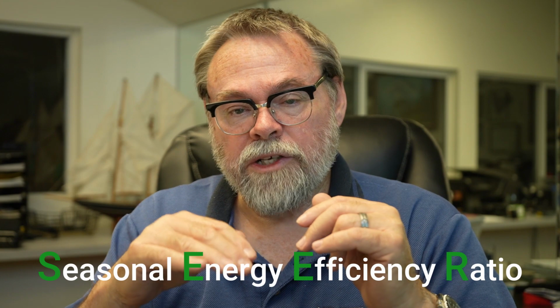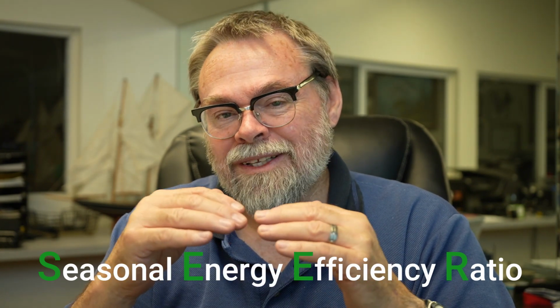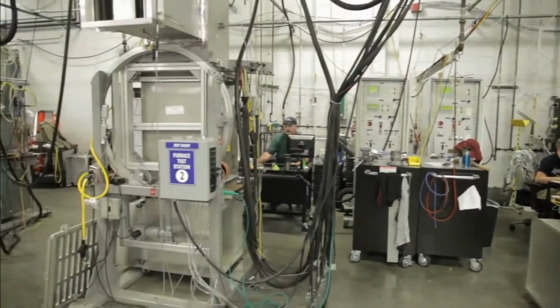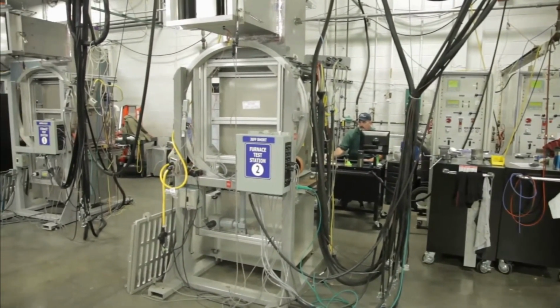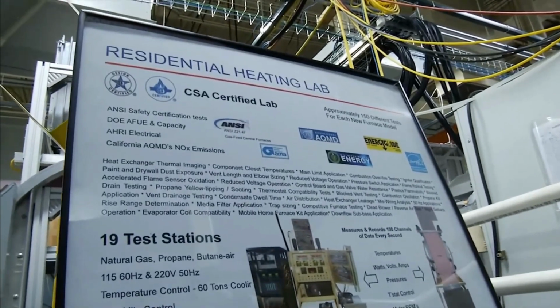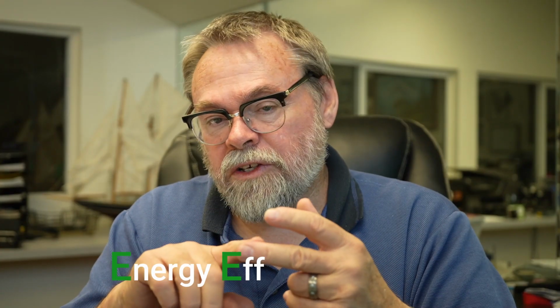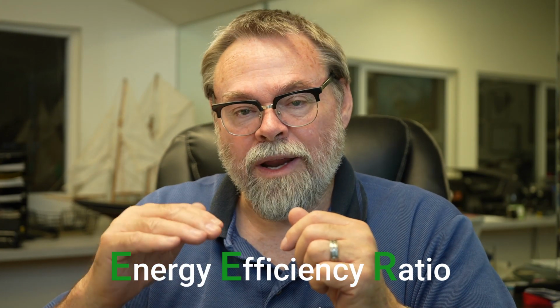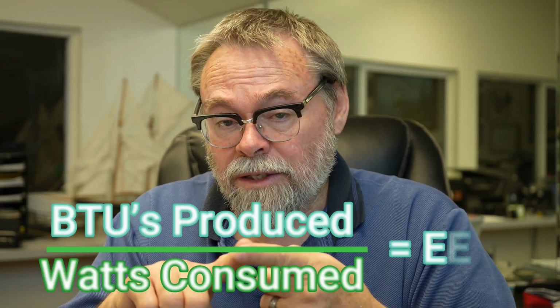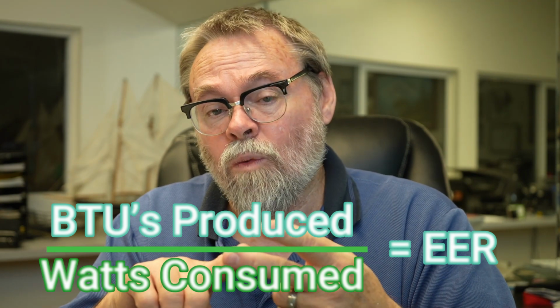Now, SEER, Seasonal Energy Efficiency Ratio, came about. It cannot be measured in the field. It has to be done in a lab, or on a computer model. What it does is take into account the starting and stopping of the equipment. EER, Energy Efficiency Ratio, is rated when the equipment gets up to steady state run. It can be measured in the field.